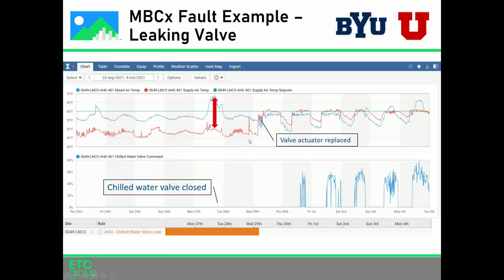This is not operating the way that we would expect it to. So we took this back to University of Utah and their team. This is an example from them. They were able to go and troubleshoot the valve and identify that the actuator was broken. It wasn't working anymore, so they were able to replace that. And here you can see right when they replace it, we get better control of the unit. We're actually delivering the temperature that it wants, and the chilled water valve is able to control as needed.